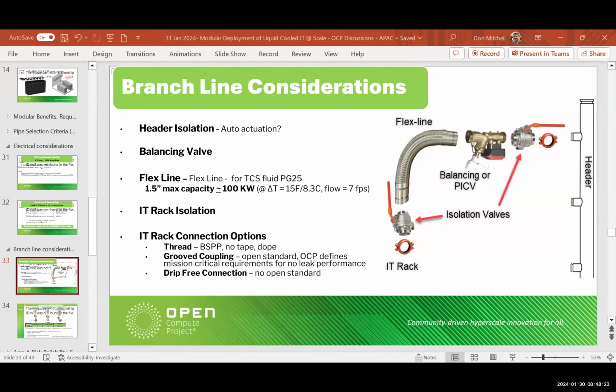Yes. So you basically have an isolation valve there, and before you open it up to the system you want to tackle getting as much air out of that drop to the rack as possible. You want to make sure it's ready to go and not send air pockets down to your CDU, or allow them to get entrained into the fluid itself, creating micro bubbles and decreasing your heat exchange efficiency.